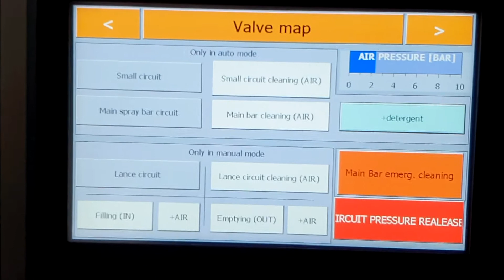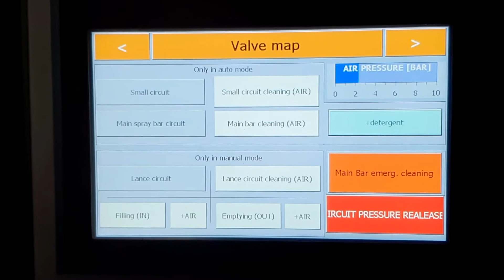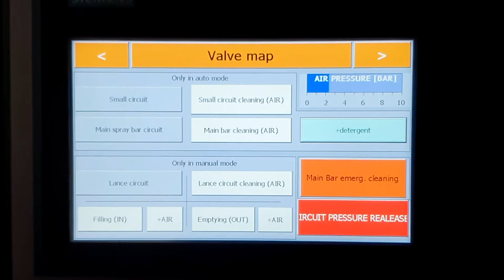Or if we want to really clean the spray bar very well, we can open the main bar emergency cleaning with this button. This will push the air and all of what is left of the residues of the detergent through the spray bar, but it will also open the nozzles. But this is a very good way to see and check for yourself if the spray bar is really empty.